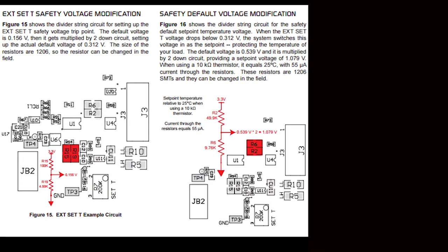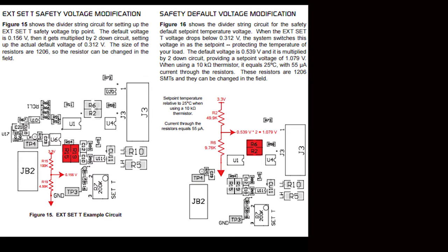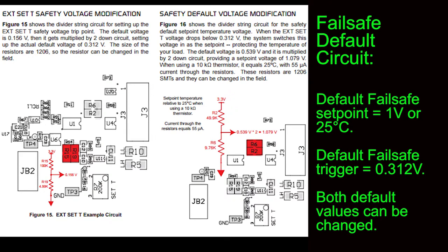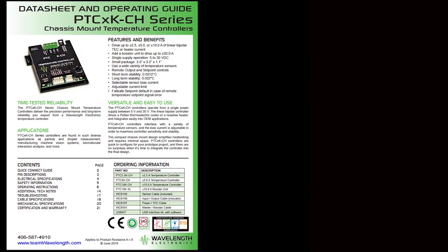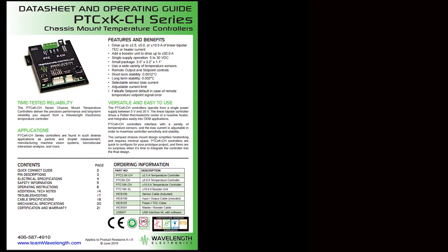If you're using an external setpoint, the PTC has an extra fail-safe default circuit to make the setpoint 1 volt if the external setpoint signal is lost. That way, the system doesn't drive the load to extreme high or low temperatures. The default trigger point is 0.312 volts. Both the trigger point and the safety setpoint can be changed. More information on adaptations is available in the additional technical information section of the datasheet.